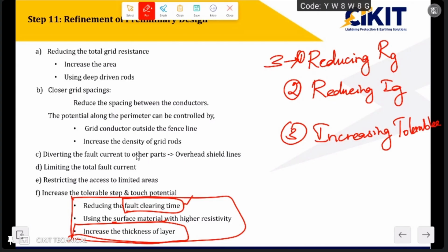The options provided for reducing Rg are that we can increase the mat sizing, or we can provide deeper earth electrodes, or we can provide closer spacing. For reducing the value of Ig, the commonly used method, we are not reducing it actually, but what we can do is connect the shield wire of transmission lines, so that some portion will get diverted. The parameter involved is Sf, the fault current diversion factor. Based upon this, the fault current value will change.